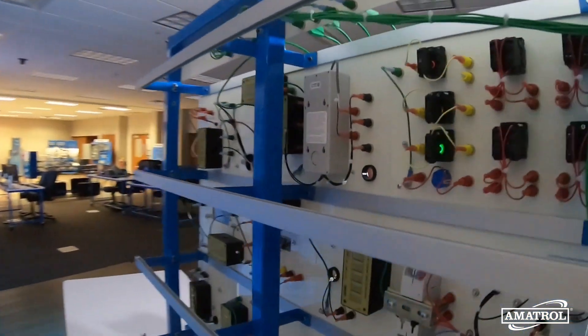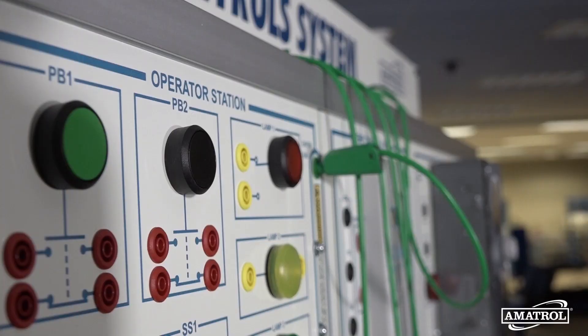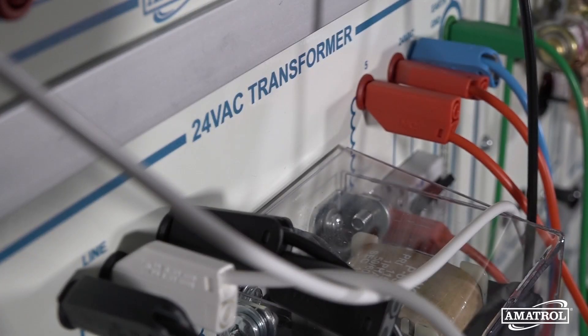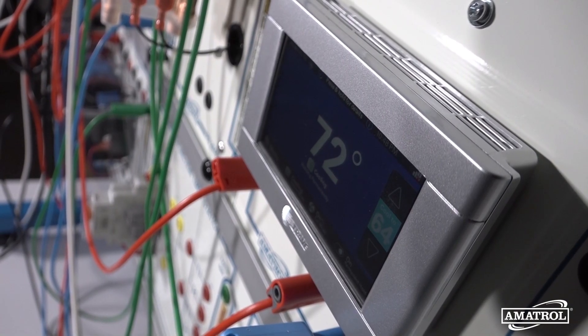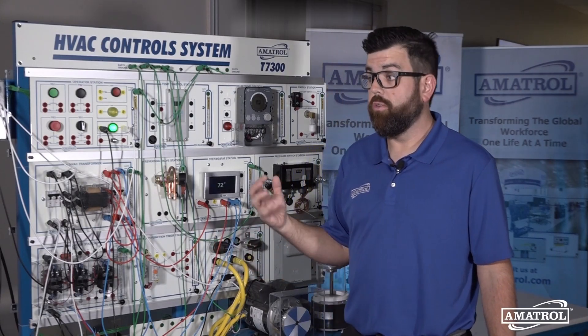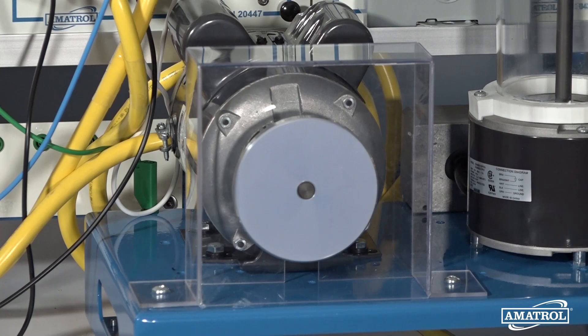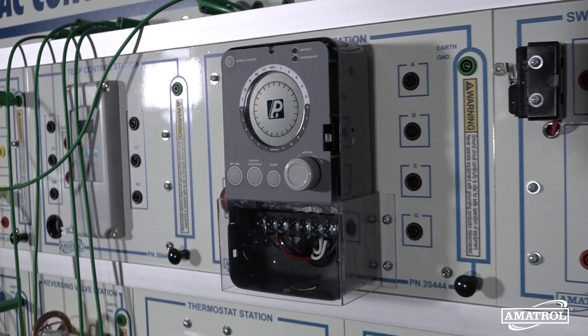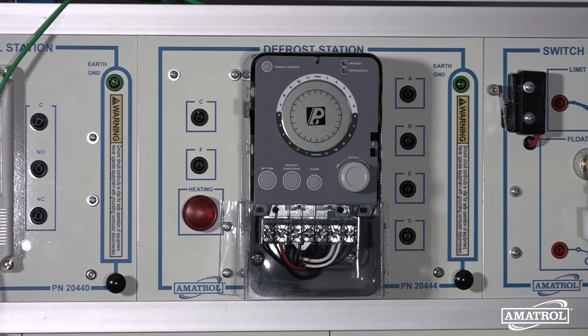It's a dual-sided system, which can open up for add-ons down the road, but currently we have 12 panels. Some are tied strictly to the motor electrical side with operator station panels, transformer, and contactor stations, but we also have HVAC focus stations such as temperature control, a thermostat station, and a defrost station. Down here you'll see three different motors — a fan, a compressor, and a blower. This is the first Amatrol system to feature a fully programmable defrost controller, which is right up here: the Paragon 9145, which can be programmed as temperature or time dependent.